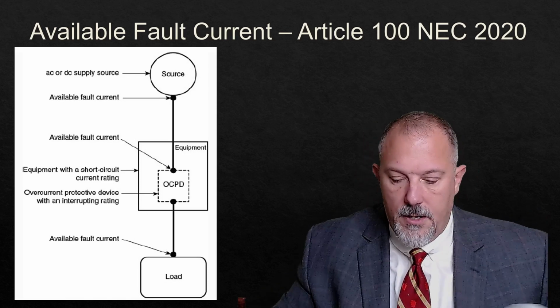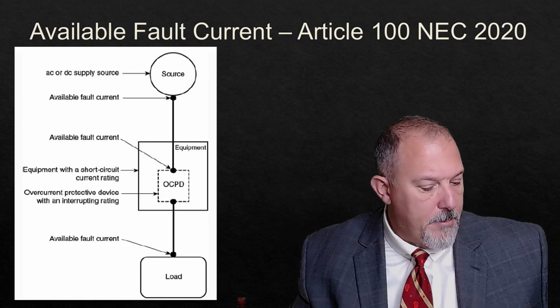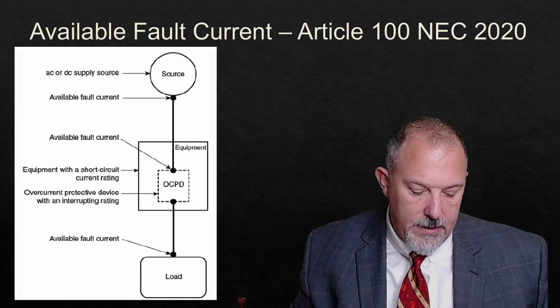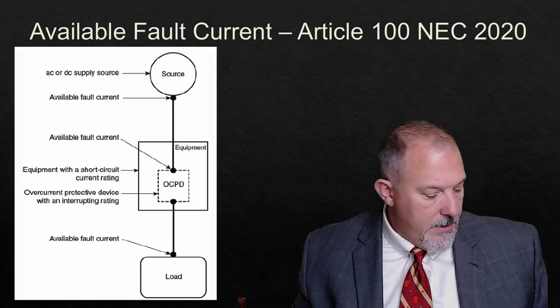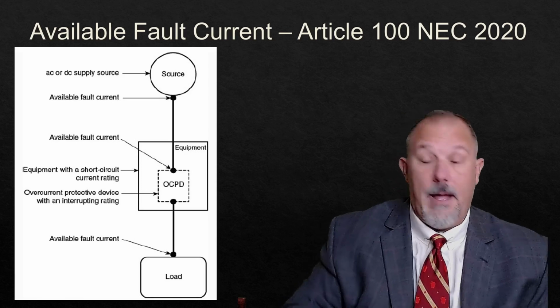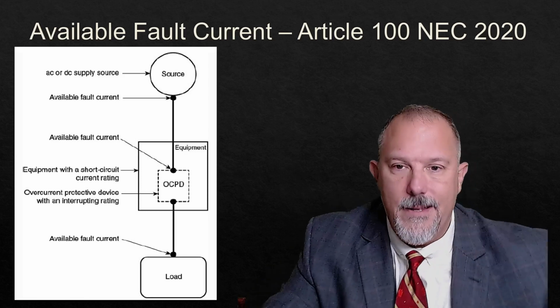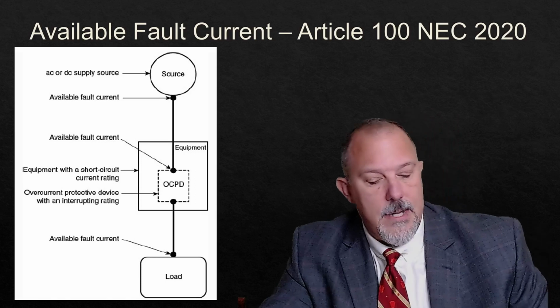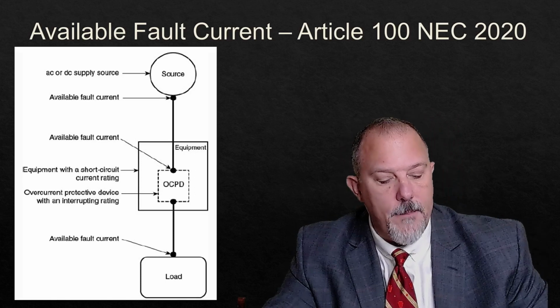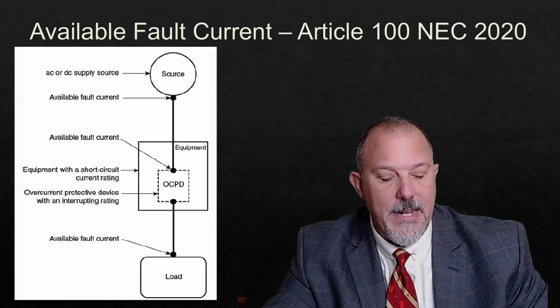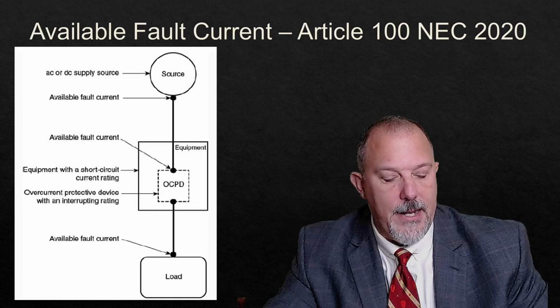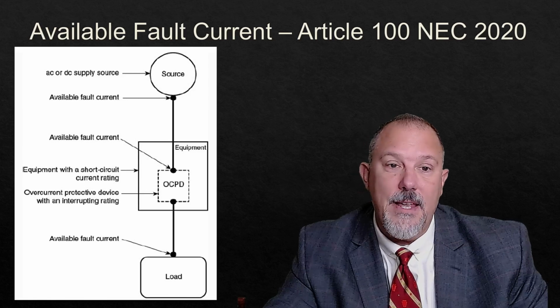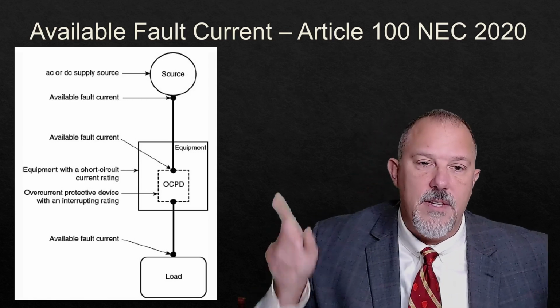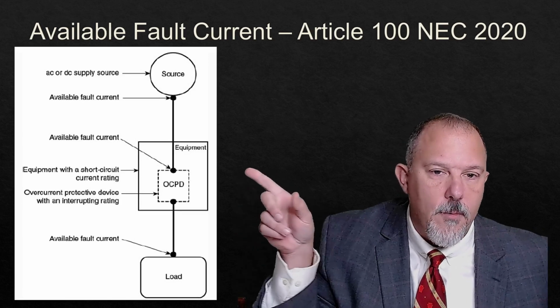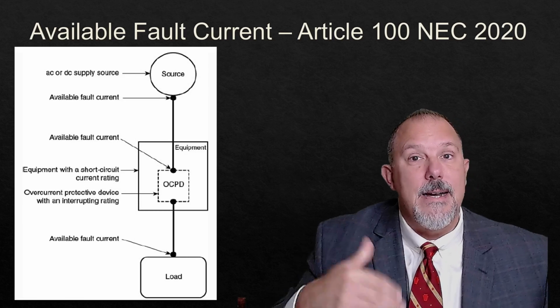Let's take a look at the section of reference in 110. I believe it's 110.9. We're going to double check my numbers. Yes, 110.9 is interrupting rating. Equipment intended to interrupt current at fault levels shall have an interrupting rating at nominal circuit voltage at least equal to the current that is available at the line terminals of the equipment. So the available fault current in this diagram, it's that one right there, because that's at the line terminals of the equipment.